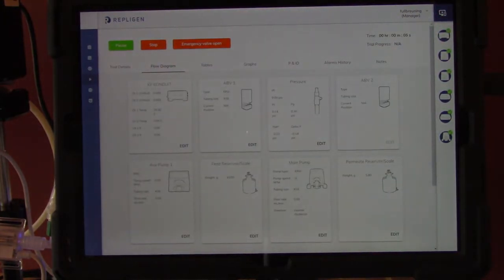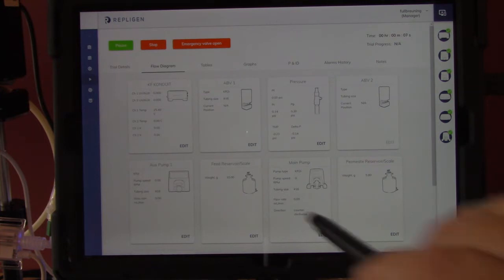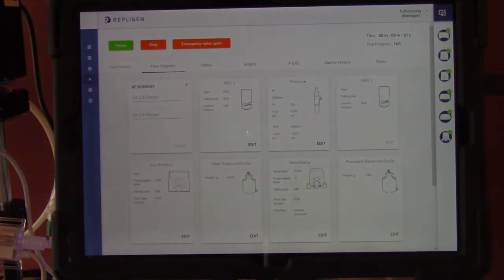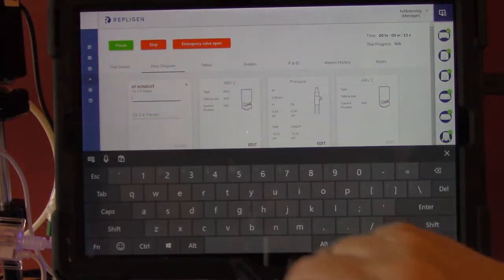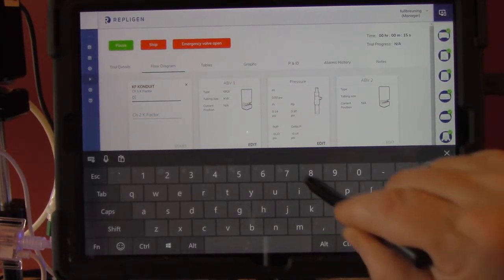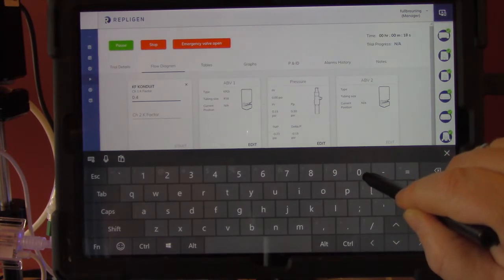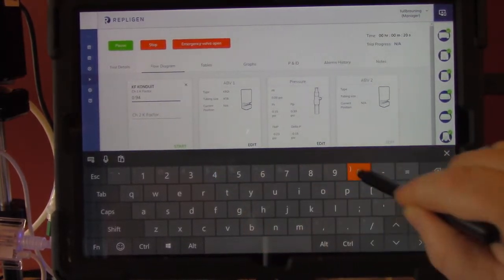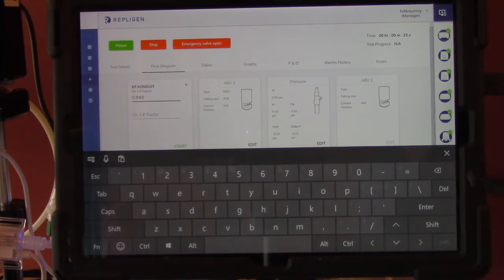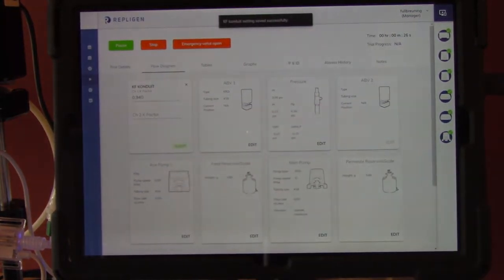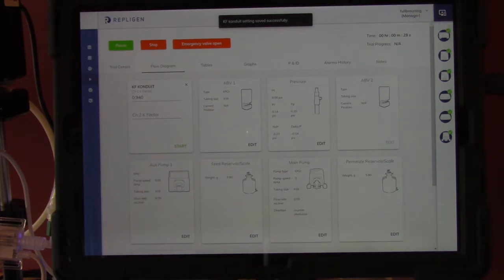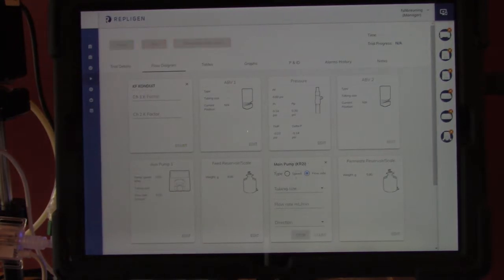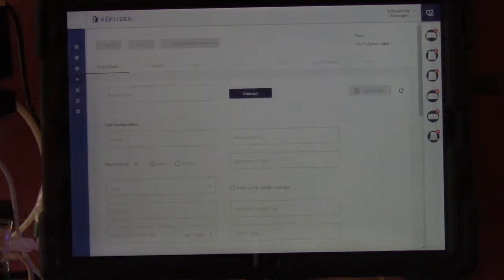Now I'm going to go to the flow diagram screen and bring up the KONDUiT. This is where I need to put in my K factor, and it was 0.943. And then hit start. That setting has now been successfully saved. I've stopped the manual run and I want to show you how to program a recipe now. Okay, now let's go program a recipe.